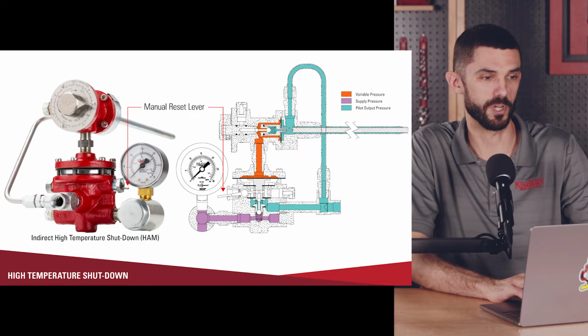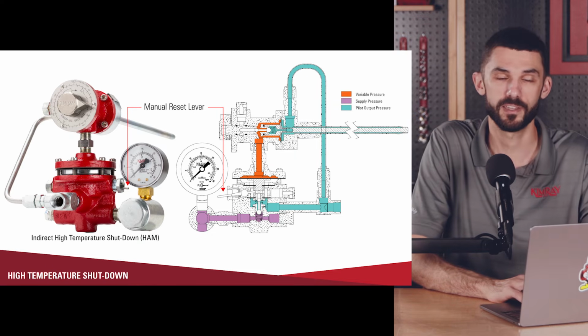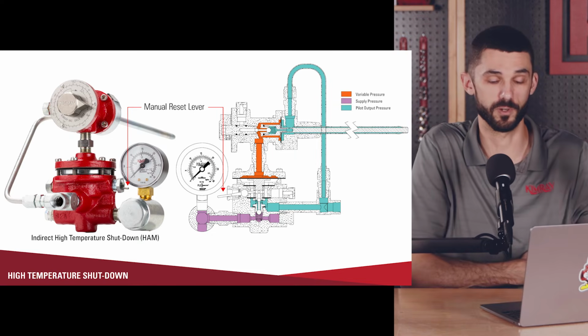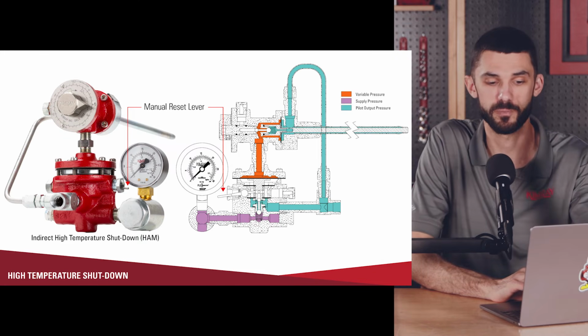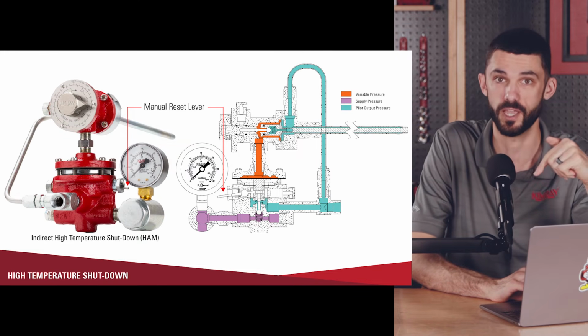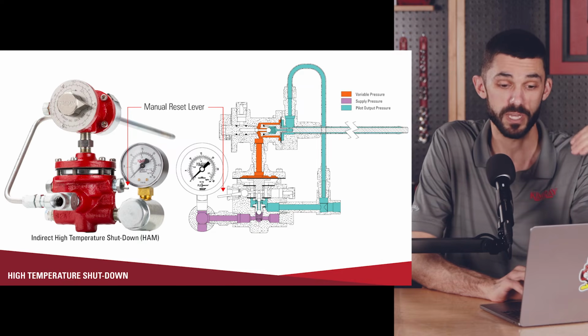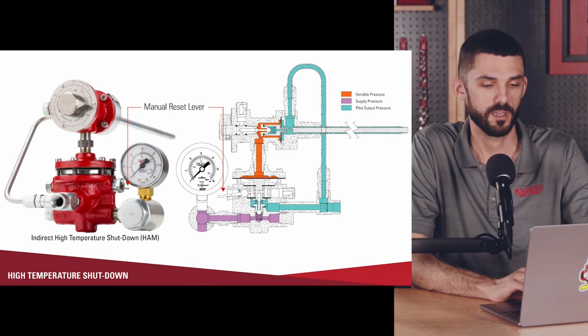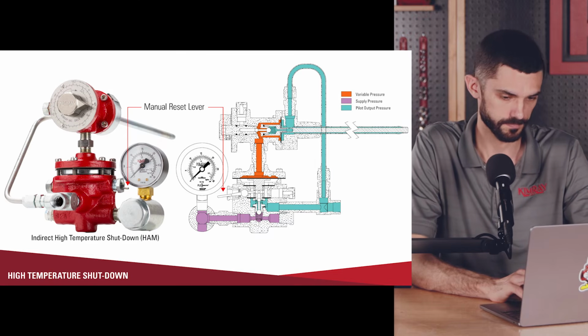Whether that's, hey, I'm not drying out my gas enough, or if you're going by and visually checking it, you can see that the switch on the side of the manual reset pilot is actuated. That would be an indication that something has gone wrong. Obviously, you want to look into what caused that upset scenario and make sure that you're fixing what has broken or what has failed before you turn things back on. But it's just a safety device to shut everything down until you can fix it.